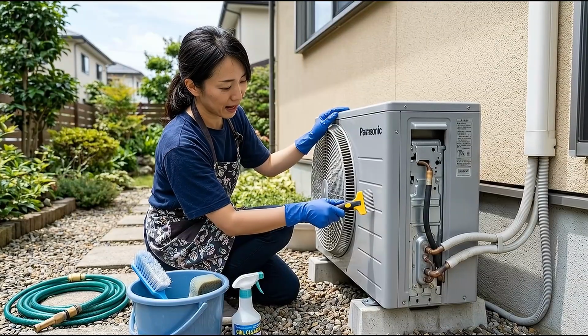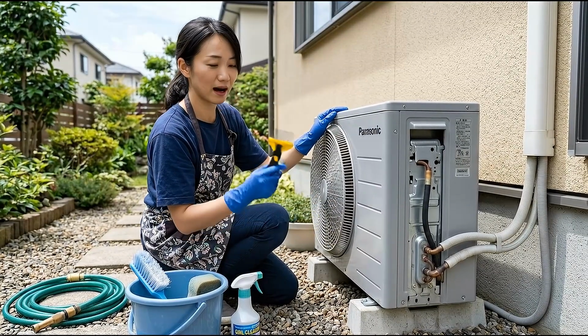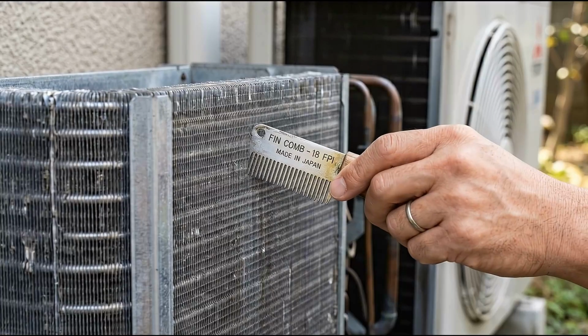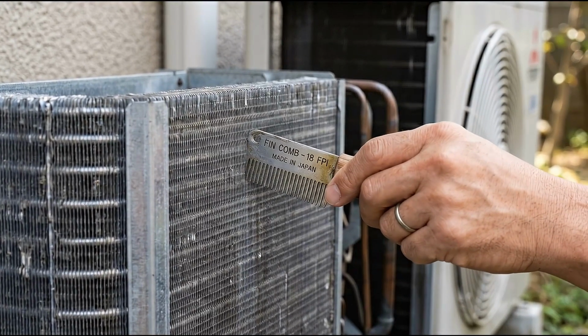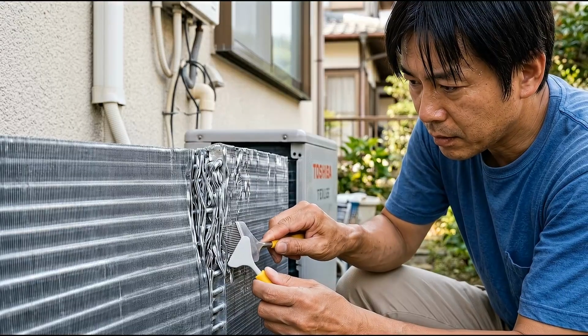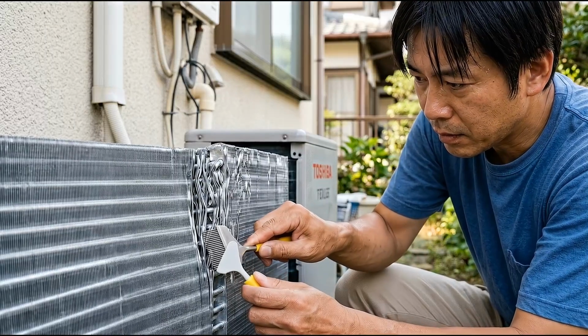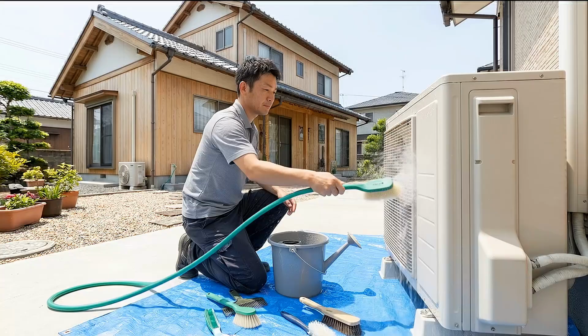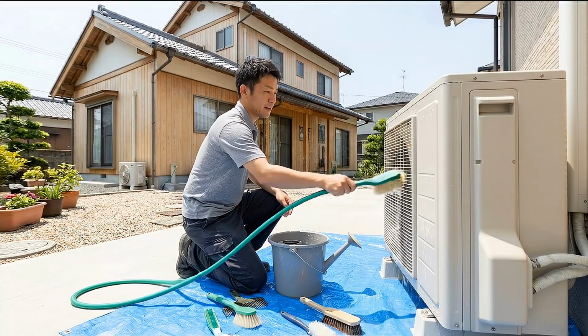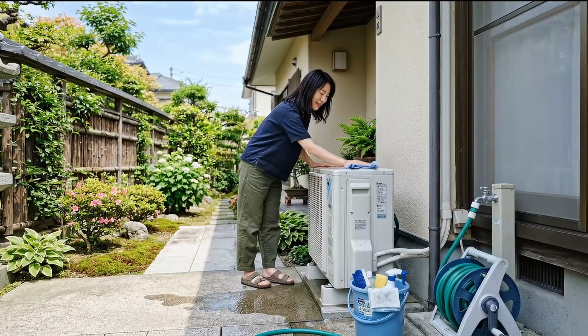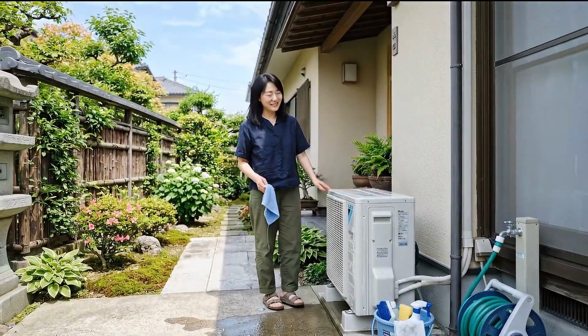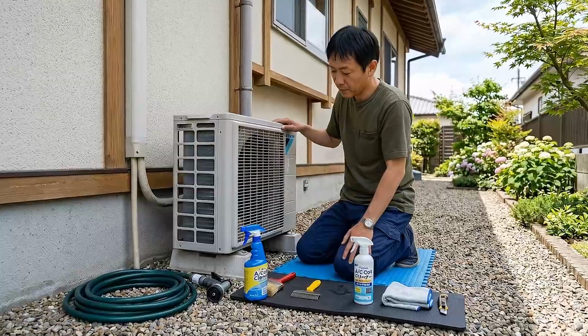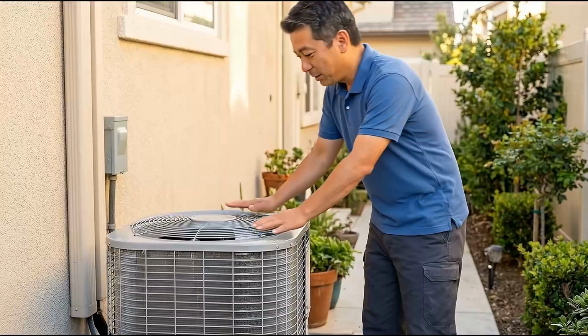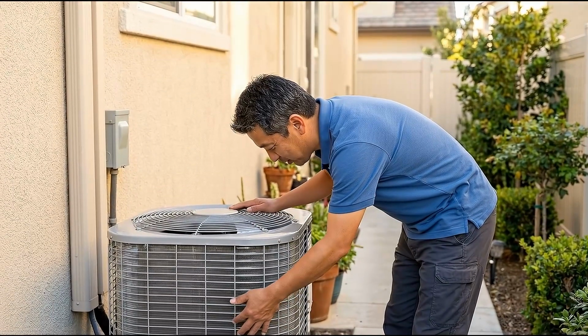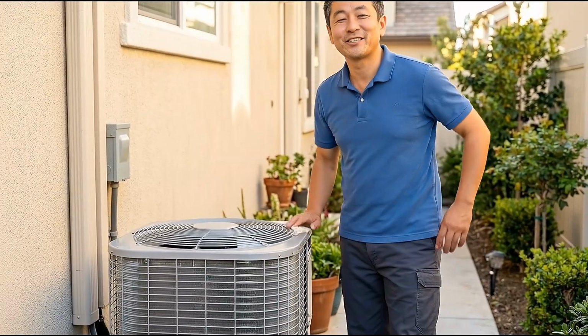You can buy one at a hardware store or online for under $10. It looks like a small metal comb with teeth spaced to match the fin spacing on your unit. Run it gently down the bent section and the fins spread back into position. That is a $5 tool doing the work of a $100 service call. This entire condenser cleaning takes about 30 to 60 minutes, once a year in the spring before cooling season starts. And the total supply cost is under $20 if you already own a garden hose. The DOE identifies coil cleaning as one of the most impactful maintenance tasks a homeowner can perform.